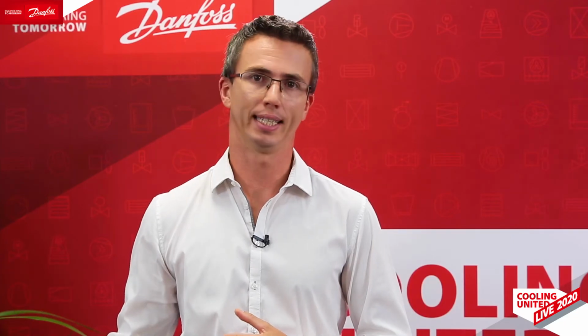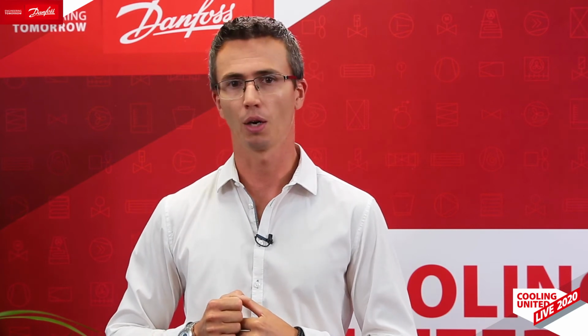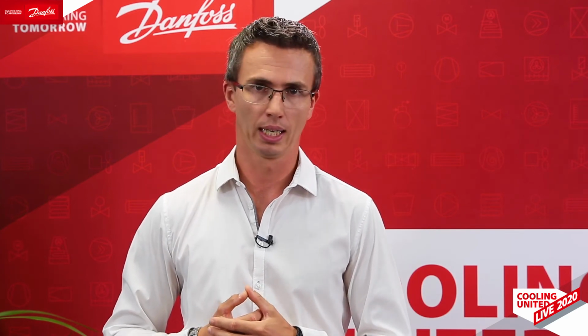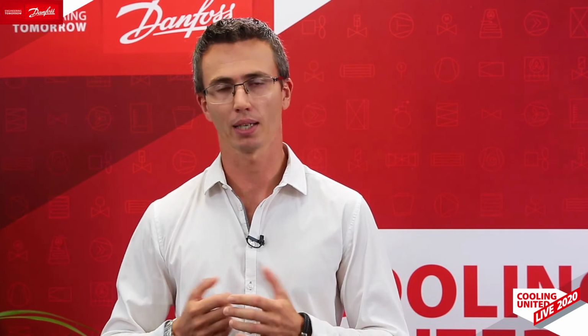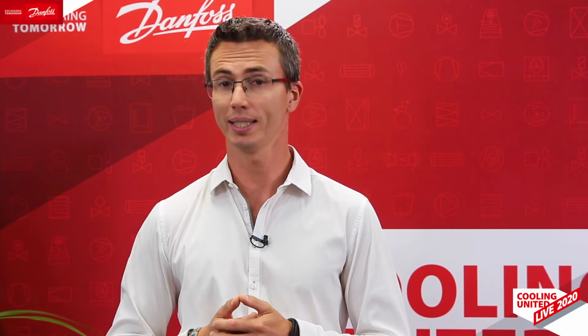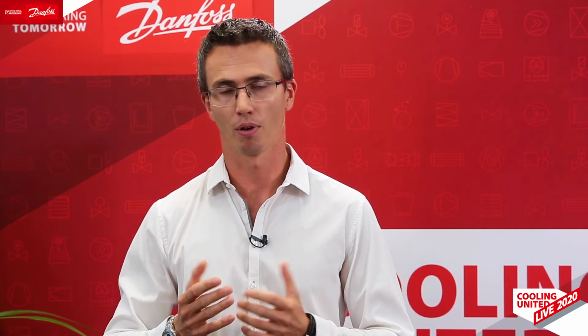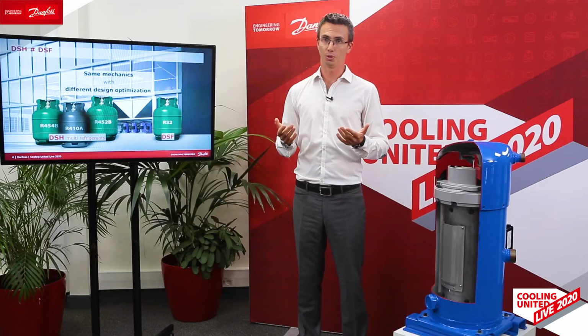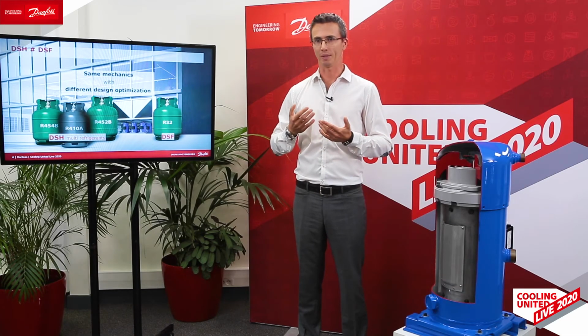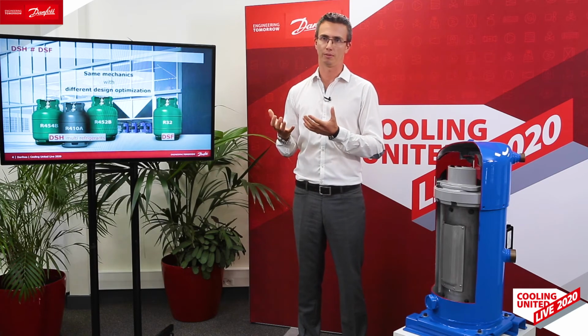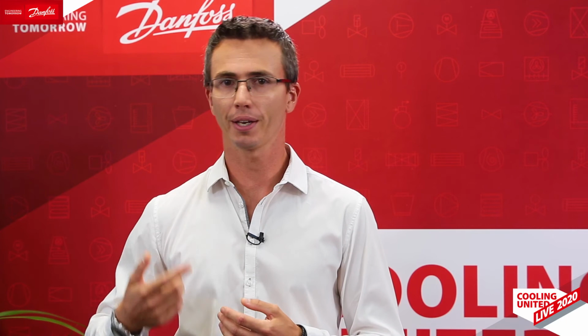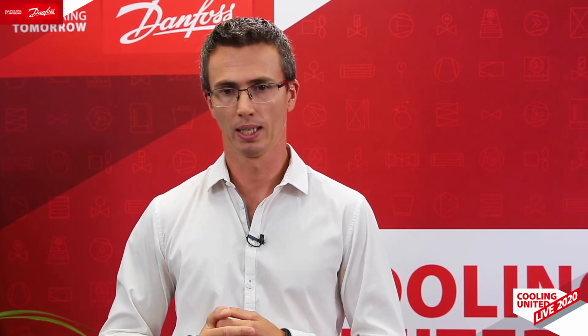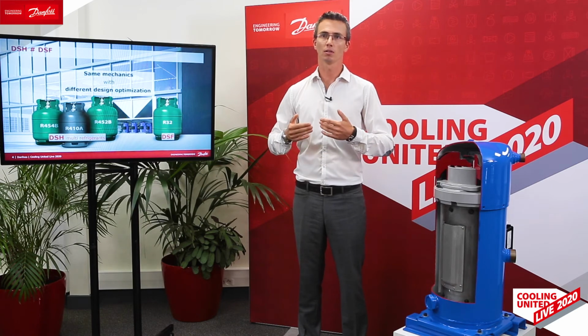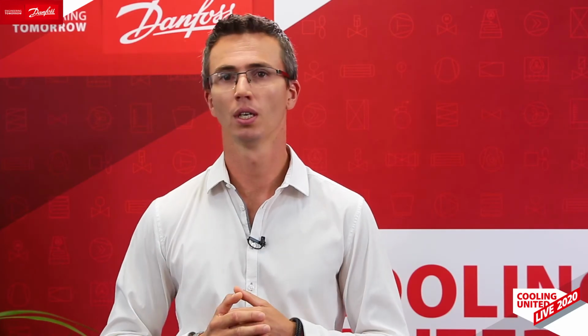On the other hand, we have DSF for R32, which is fully dedicated and optimized for R32. And its design succeeds to bear the impact of high discharge gas temperature without the need of costly liquid or vapor injection. And this is, for the same platform, a significant applied cost benefit. But to do so, you will need a broader system redesign. That means that the component selection should be different: heat exchanger, for instance, piping, valves, and so on. And also because oil is different and behaves slightly differently. But if you do so, then you will achieve an optimized applied cost, definitely.